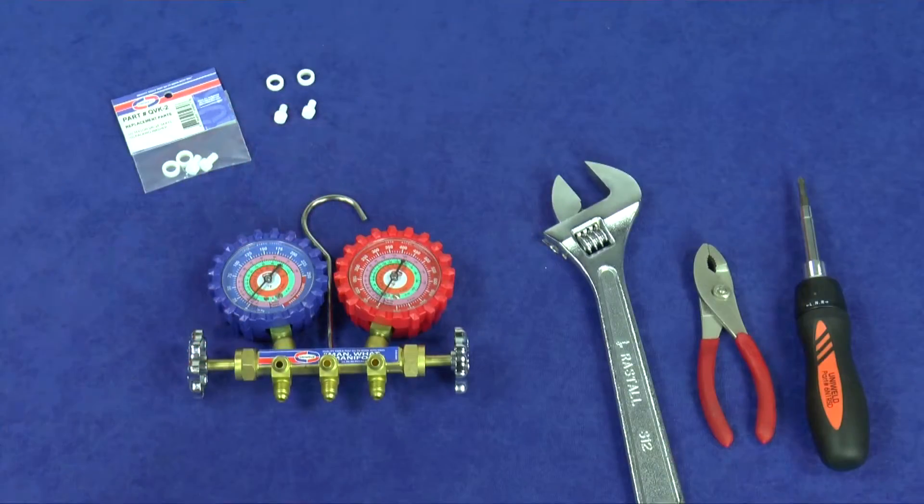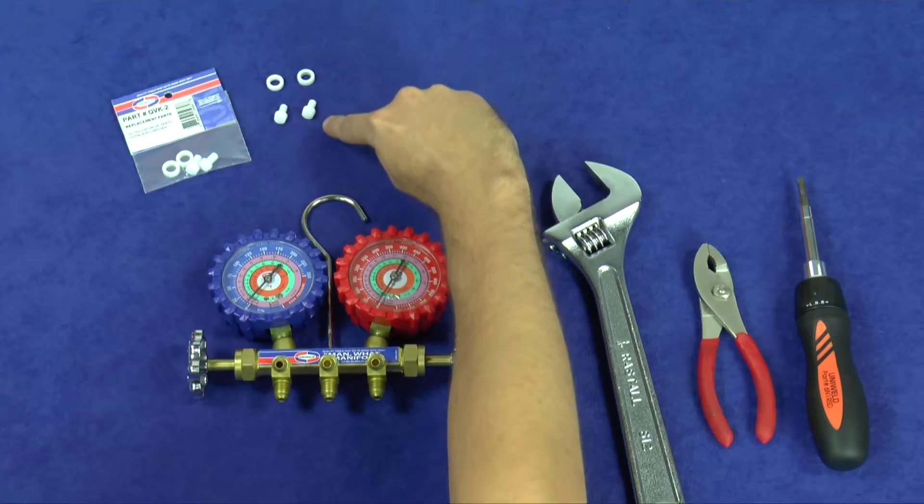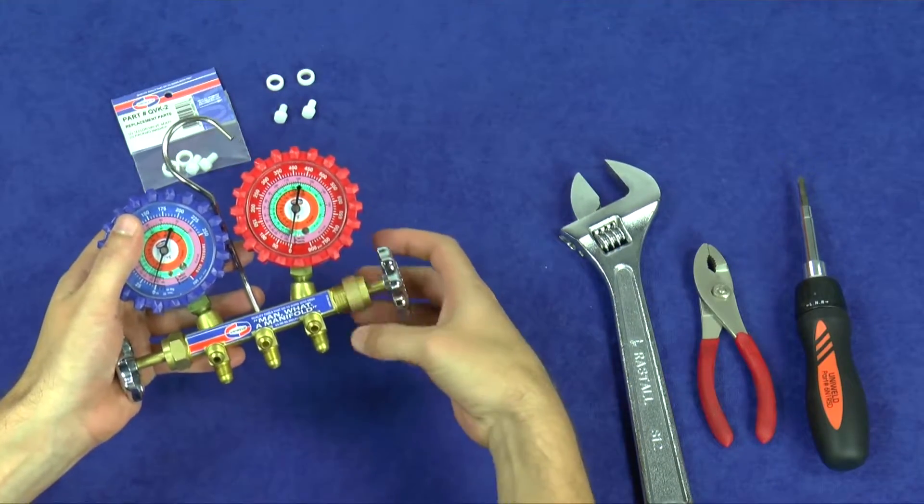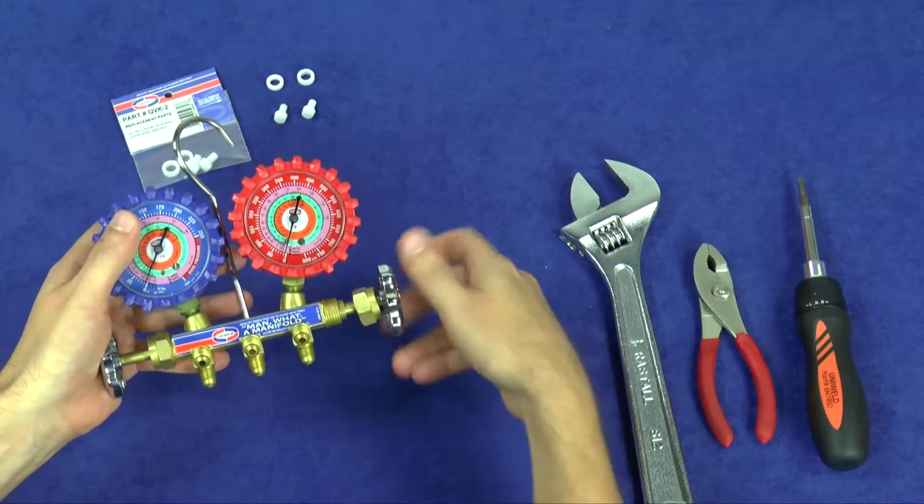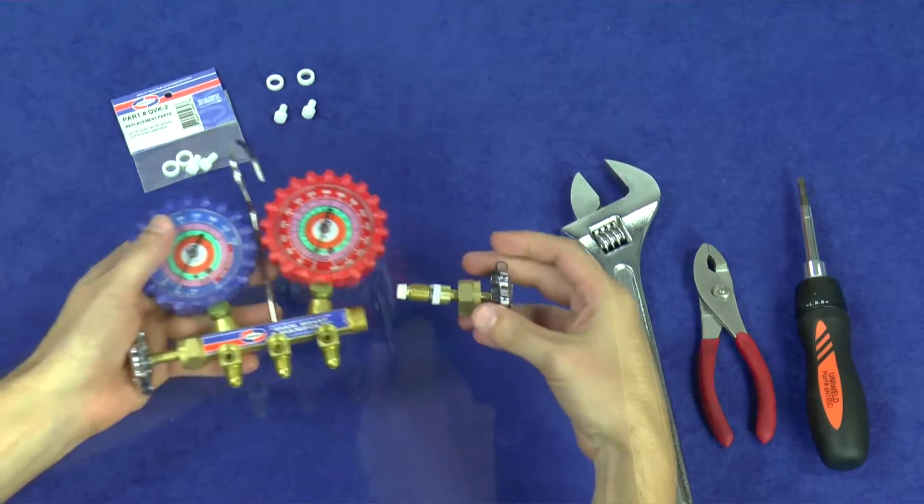The second option, the QVK2 rebuild kit, includes two Teflon washers and two Teflon valve seats, allowing you to rebuild both the high and low side valve stem assemblies. First, unscrew the brass packing nut and remove the valve stem assembly from the manifold body by turning the metal hand wheel counterclockwise.